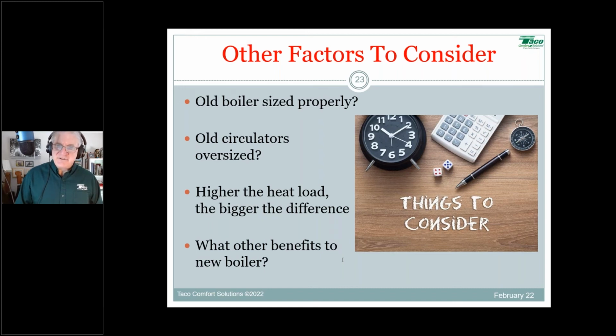If you want to vary the speed of a circulator, shouldn't you vary the speed in a way that accurately reflects the load? And the delta T is going to determine the load. Remember, the universal hydronics formula states that GPM, your gallons per minute flow, equals the BTUH load divided by the product of delta T times a constant. In this case, we'll use 500.